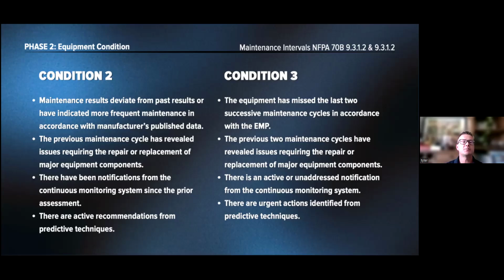The previous maintenance cycle has revealed issues that require repair and replacement of major equipment components. That's another high level one to be on top of. When doing your active maintenance cycles, you're able to identify critical equipment with serious lead times, so you can budget accordingly and get that order before it actually fails.